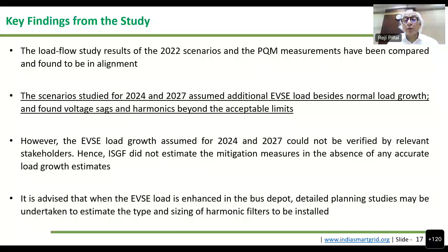So it is advised that when EVSE load is enhanced in the bus depot, detailed planning studies may be undertaken to estimate the type and sizing of harmonic filters to be installed in the bus depots. The recommendation for electric utilities is that wherever you are giving an HT connection at 11 kV, 22 kV or 33 kV to a bus depot or other public charging stations, detailed engineering drawings along with equipment sizing calculations of the electricity distribution network within the bus depot must be verified and approved by the utility before sanctioning the HT connection.